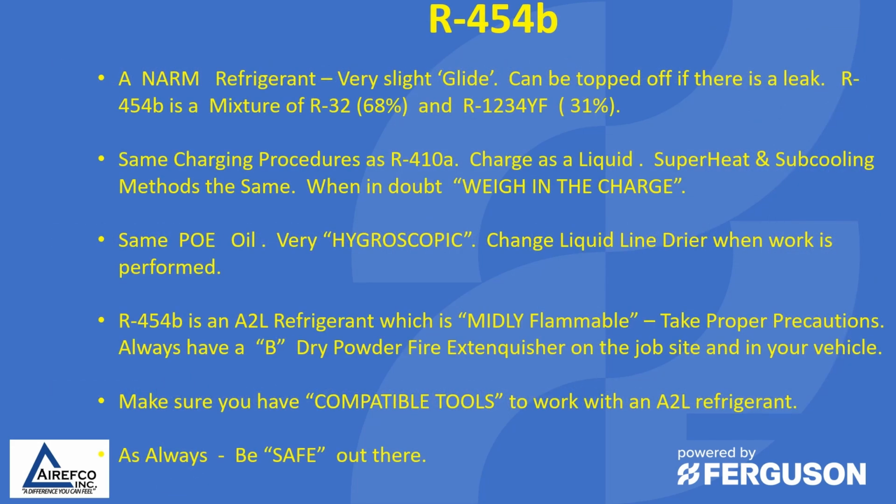So let's look at a few considerations regarding R454B refrigerant. A NARM refrigerant has a very slight glide and can be topped off if there is a leak. R454B is a mixture of R32 at 68% and R1234YF at 31%.